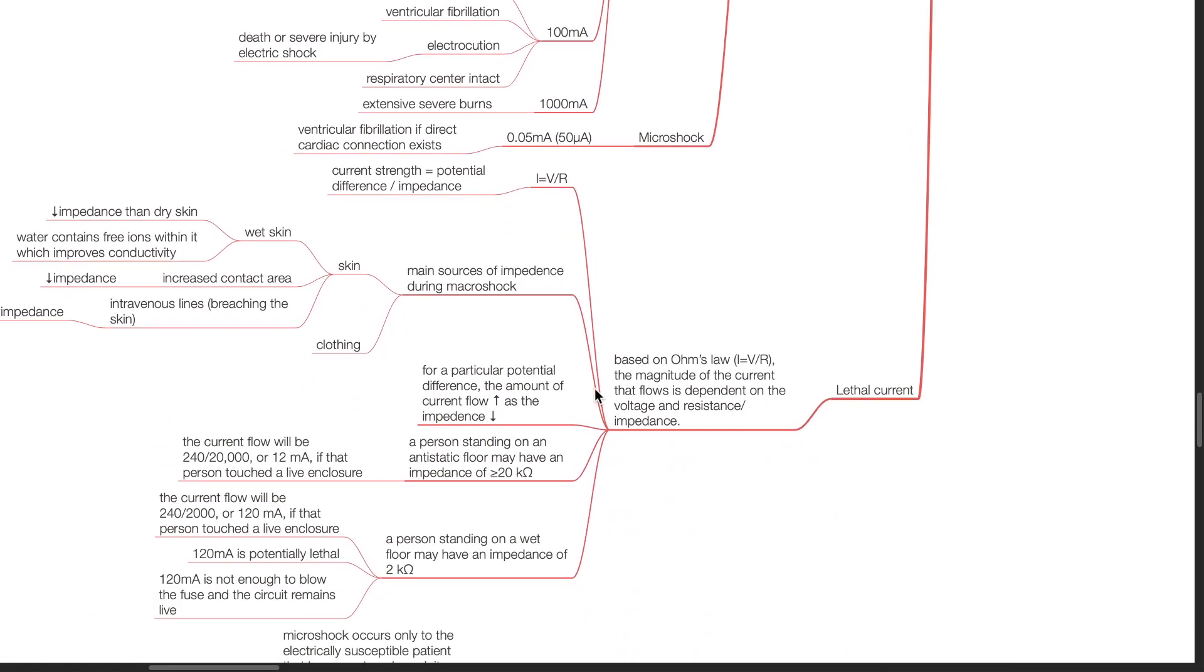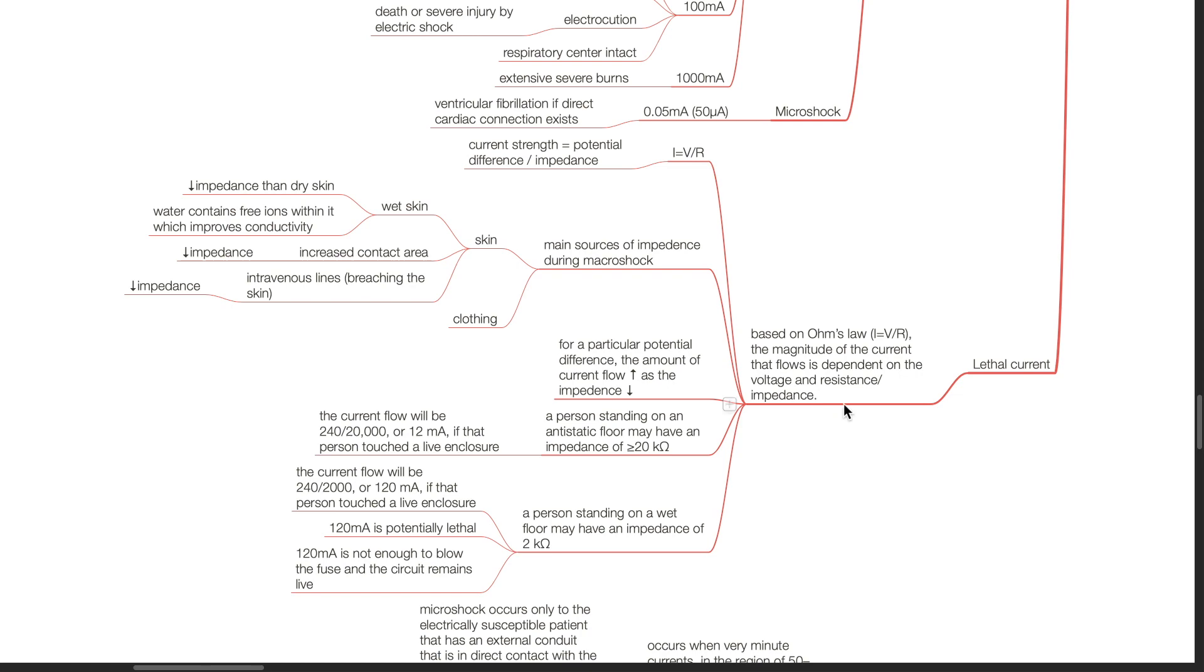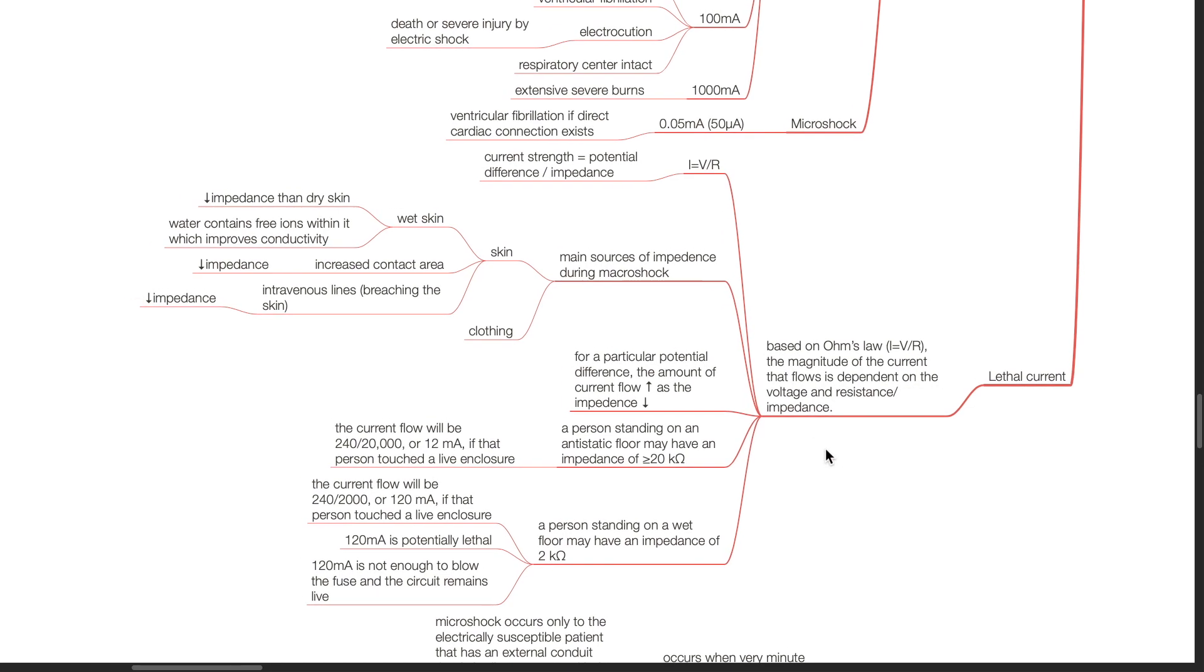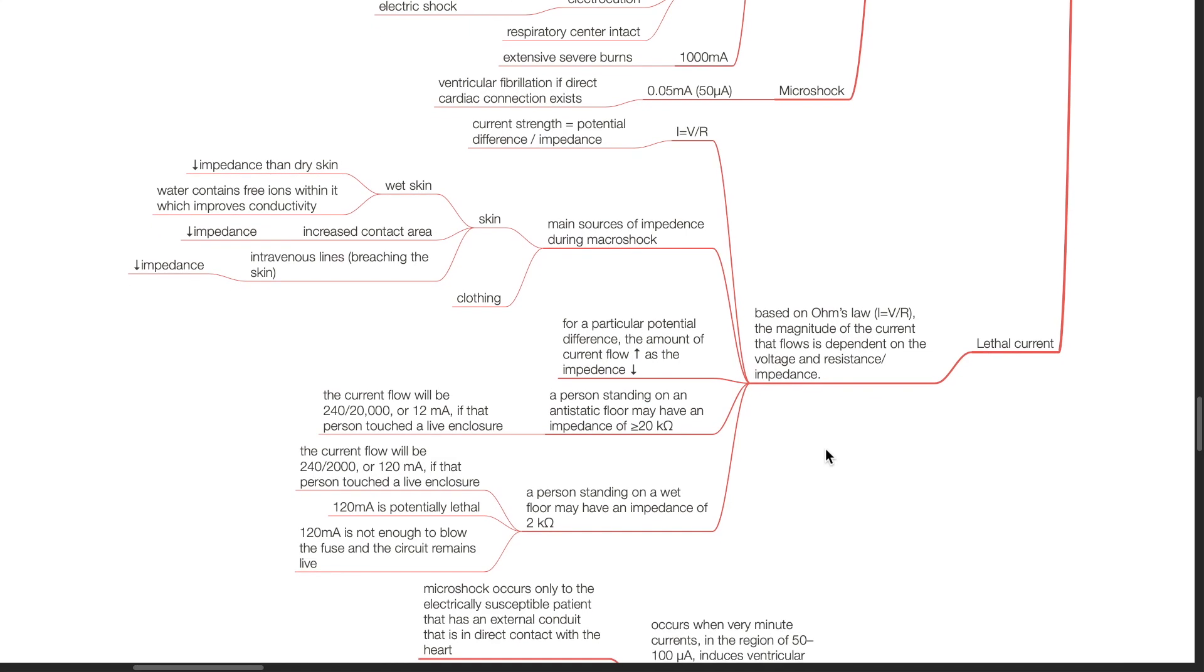Lethal current. Based on Ohm's law, I equals V divided by R. The magnitude of the current that flows is dependent on the voltage and the resistance or impedance. Main sources of impedance during macroshock include the skin and clothing as mentioned previously. For a particular potential difference, the amount of current flow increases as the impedance decreases. A person standing on an anti-static floor may have an impedance of more than 20,000 Ohms. The current flow will be 240 divided by 20,000 or 12 mA if that person touched a live enclosure.